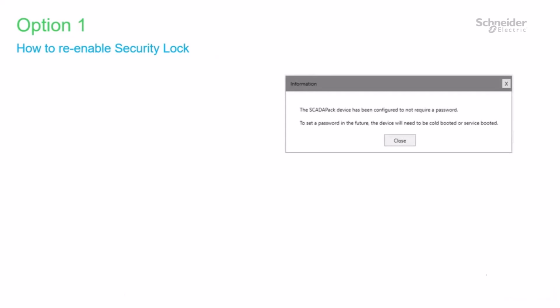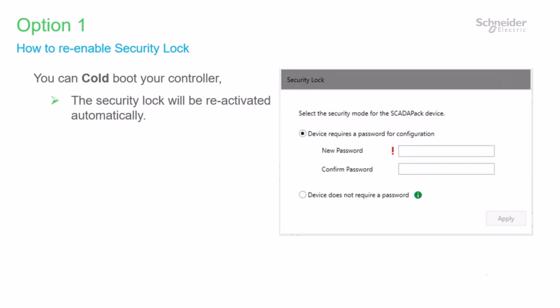So how would I re-enable the security lock? On the information message we looked at, it tells you that you need to do a cold boot or service boot. Doing a cold boot, the security lock will be reactivated automatically, and when I select Online, I'll get this dialog again. I can then apply a password and enable security locking. But a cold boot erases controller data, so that's a bit severe just to re-enable the security lock.